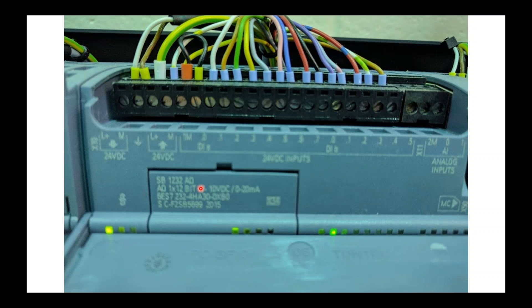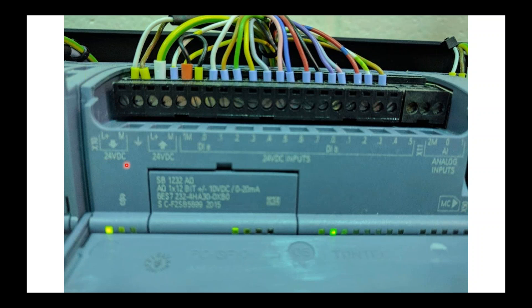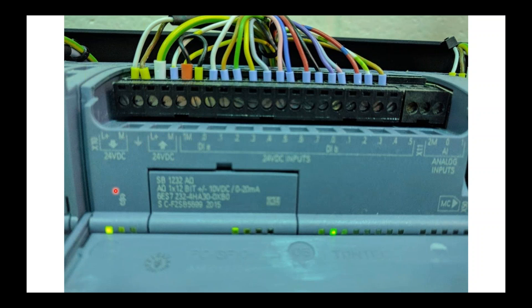With the flap down, you can see how these get programmed. Over here, you can see L plus and M input. This is where you power your processor. This is asking for 24 volts VDC. You may see that it requires 120 AC. Just read carefully. This is your ground wire here and this is an output. This processor has an internal power supply embedded in this that has some capability to power your inputs and outputs. So be aware of that.